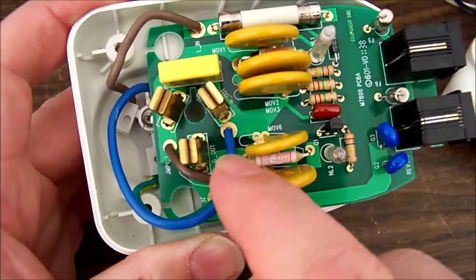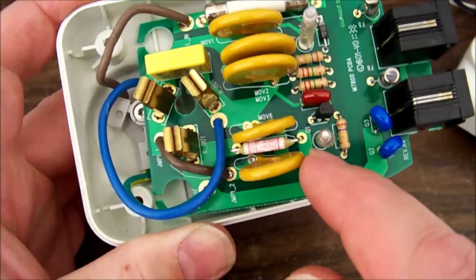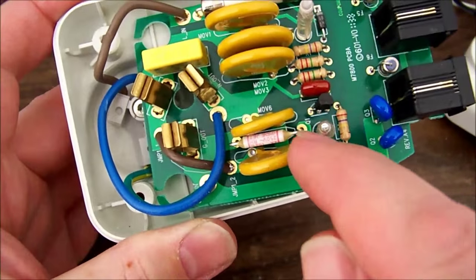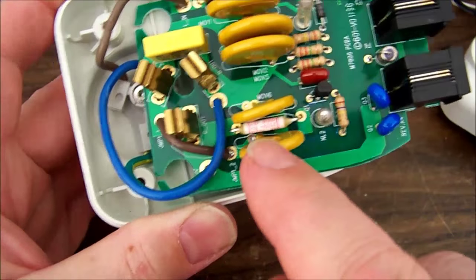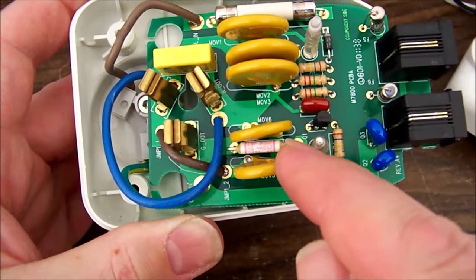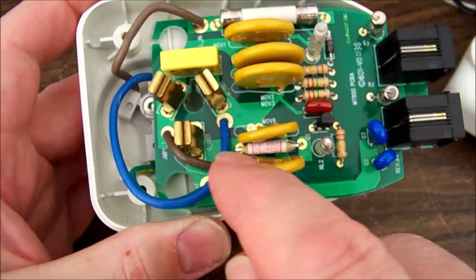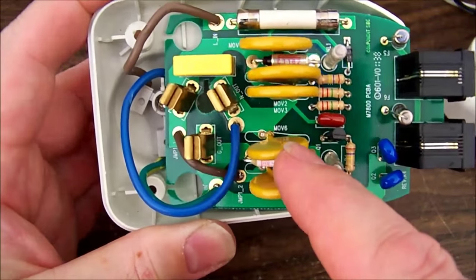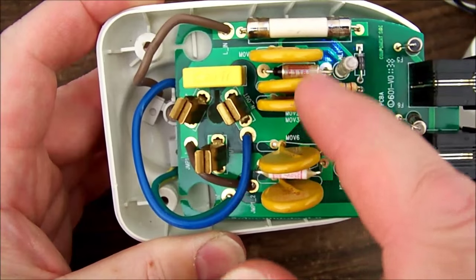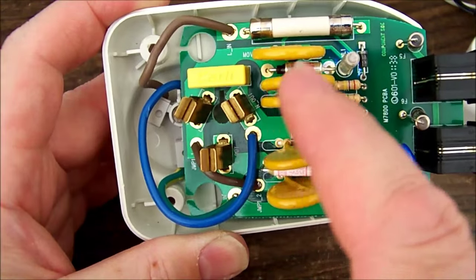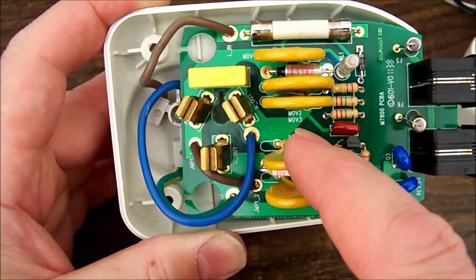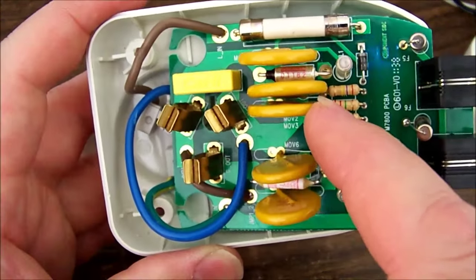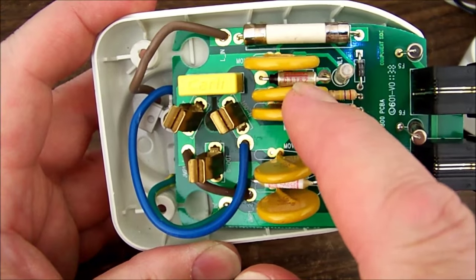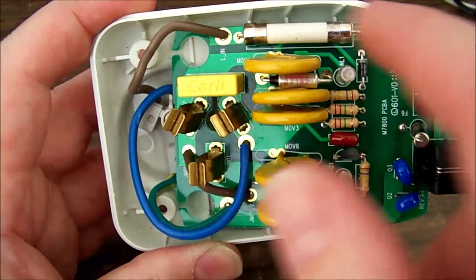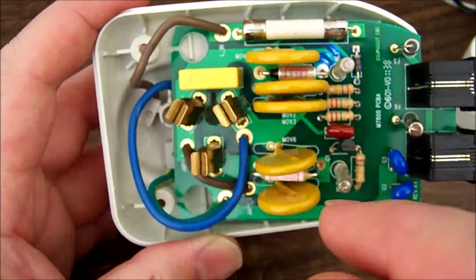What we can see here is we've got one MOV that goes from neutral, on the underside, to this fuse on this side, and then we've got another MOV that goes from phase to that fuse as well. That fuse goes through to ground, so that would be suppressing transients across phase and neutral. Up here we've got three MOVs that go from phase straight across to neutral as well. That fuse there is just in line with this fuse up here, so it comes in through that fuse and through that fuse and then off.